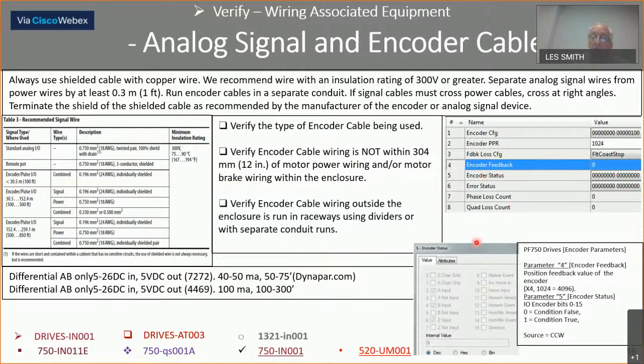Encoder status, which is here. It's hard to troubleshoot an encoder because the screws are so small, but you can just look here, and that brings your points up here for B or B not. If you have a check mark on every other one, it's healthy. But when you get check marks close to each other, then you may have a potential problem. Pull that connector off and you'll see those check marks come together, and you'll see a fault show up on that.